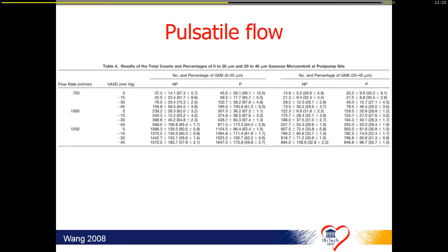And what if we then combine the worst situation? We combine vacuum assist together with pulsatile flow. The problem with pulsatile flow is the fact that you create extremely high velocities for a short period of time inside the fiber bundle, meaning that the depth filter function normally will be disturbed if there is micro air present in this bundle.